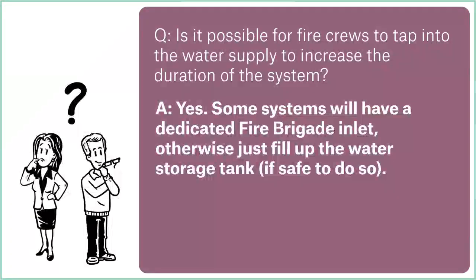The fire and rescue service, when they arrive on site, are obviously going to have a look at what the fire's doing, how it's spreading, how the sprinkler system has tackled it so far. So they've got some options there. And if they want to, they can boost the duration of the sprinkler system by feeding into the inlet. If it's a reduced capacity tank, then even more so. That'll be very useful to do.